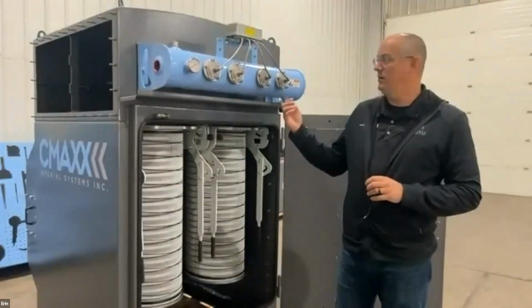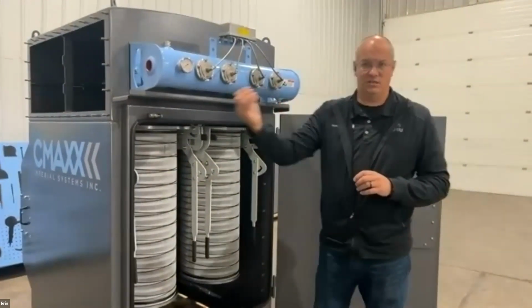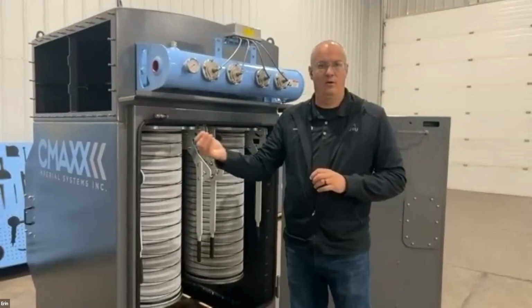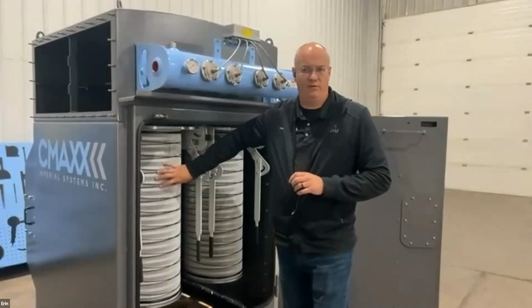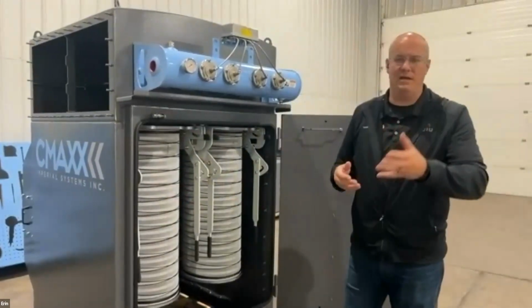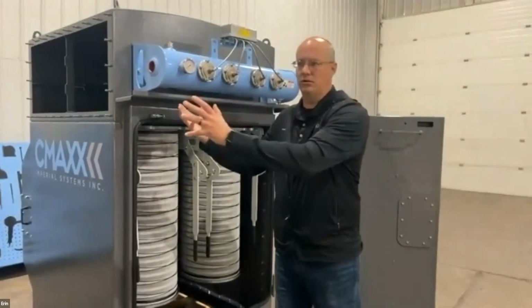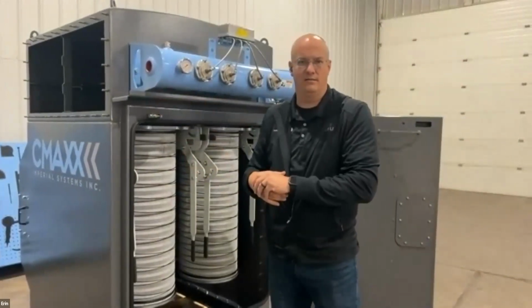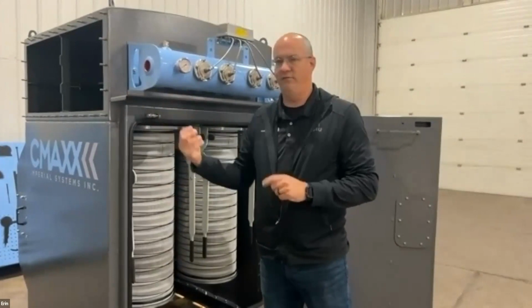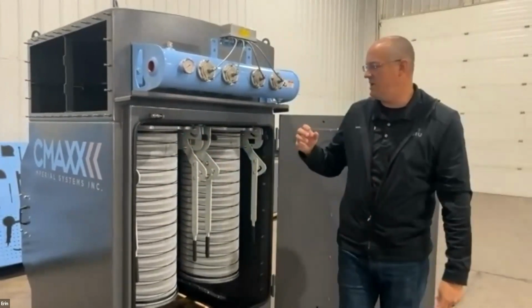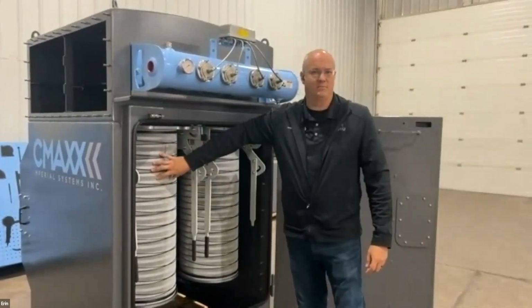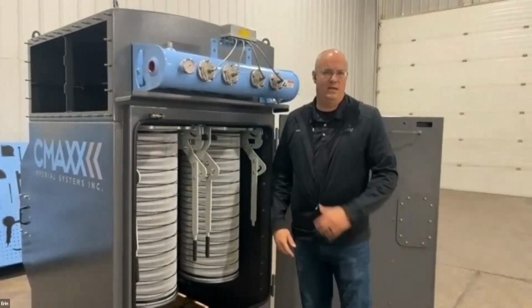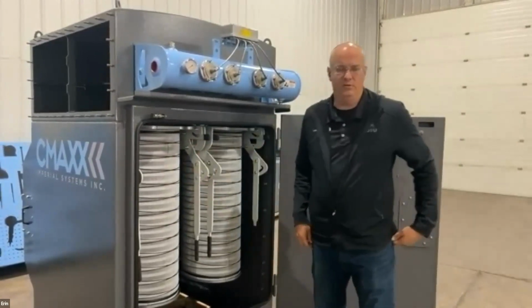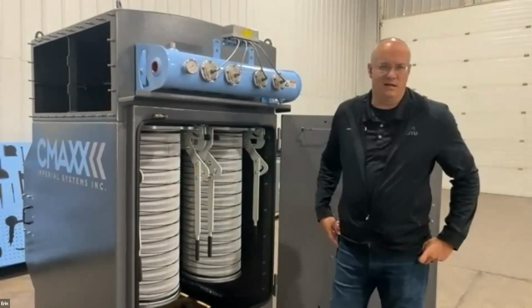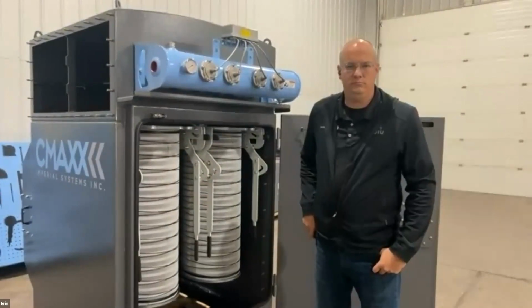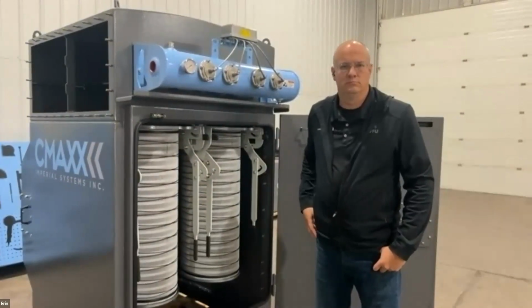So that's where an external factor such as shop air, wet shop air, can start to affect the life of your filters. And so that's why we always recommend for a couple $100, you can put a dry air system in place, or a filter that we were talking about, and it's going to save you possibly a lot of life on your filters, and nobody having to worry about that or go up and do the maintenance on it. So this is like old temperature control pneumatic air that you needed, like you'd buy a little air compressor.